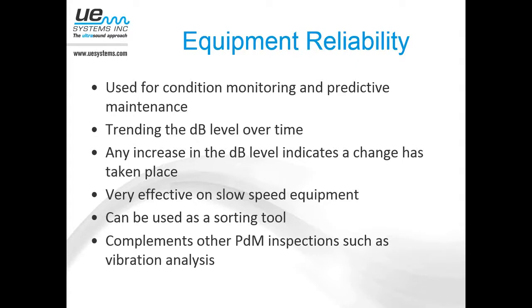If there is a change, then we want to record a wave file with ultrasound, look at it, and maybe bring in our vibe guy to have a look as well to see what's caused the change. Has the bearing entered a failure mode, or does it just need lubrication? There are all kinds of scenarios that can cause the decibels to go up, so we use it hand in hand in many cases with somebody's vibration program.